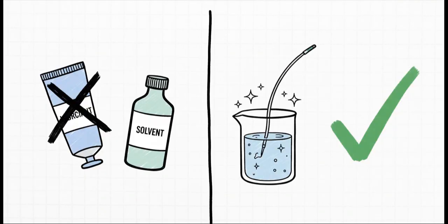And I have to pause here because this is so important. Do not, I repeat, do not use any lubricant, gel, or solvents. The catheter has this special hydrophilic coating that's only activated by sterile water. Anything else is going to mess with its function and could even damage the electrodes. It is an absolutely critical safety step.